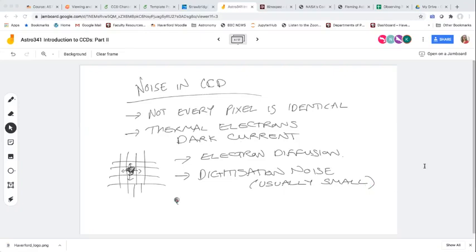And then there's the readout noise. With the process we talked about, shifting the rows and then reading out each row, each transition can introduce a very, very tiny error. They're very tiny in today's big CCDs, but the cumulative 4096 by 4096 steps that the most distant electron takes can actually introduce quite some noise. We can measure this noise by just reading out the chip without exposing it at all. We basically say everything should be 0, but let's read out the chip.